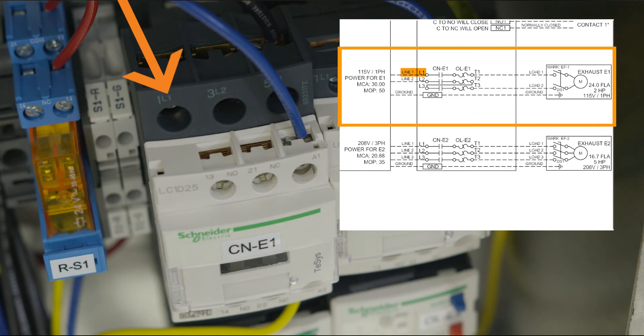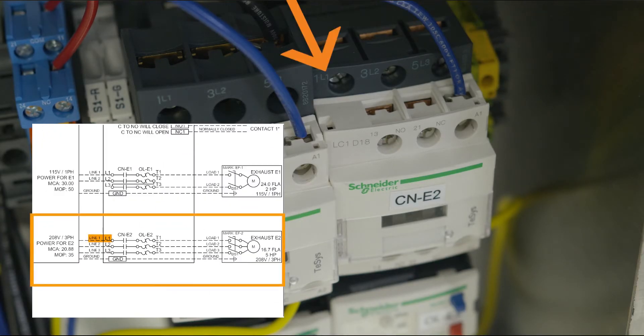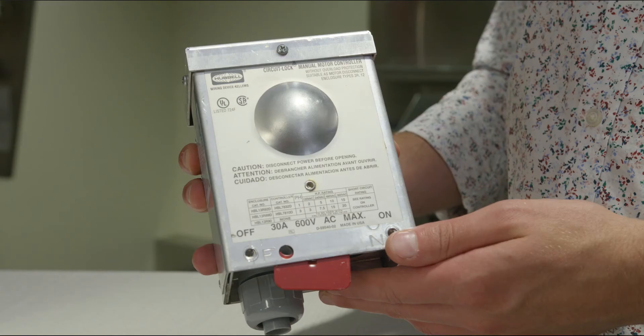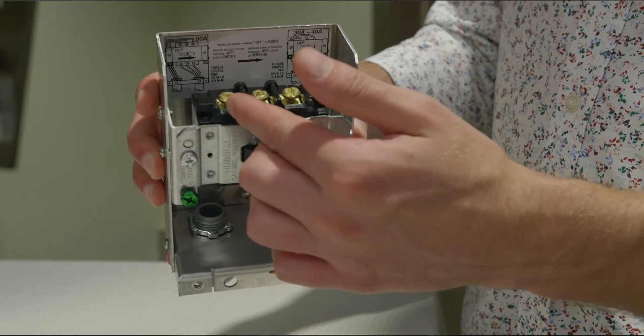We'll first look at a single phase exhaust or supply fan operated with a motor starter. Bring the appropriate voltage to the motor starter, which is typically located in the control enclosure or cabinet. Land the line power lead to terminal L1 on top of the contactor and the neutral wire to terminal L2. Then, from the bottom of the overload or contactor if no overload was provided, connect terminals T1 and T2 to the disconnect at the fan. Three phase exhaust or supply fans with motor starters are very similar. Land the three line power leads to terminals L1, L2, and L3 on the top of the contactor. Then, from the bottom of the overload or contactor, connect terminals T1, T2, and T3 to the disconnect at the fan.